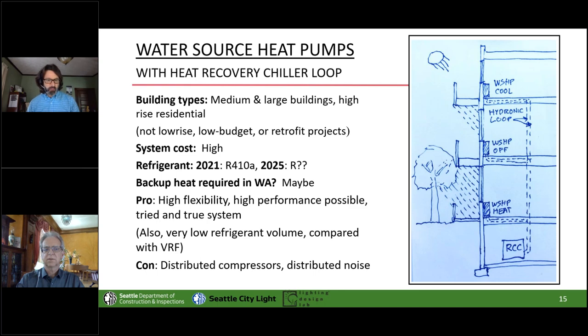Great. Now we're getting to the point where we've got these heat pump chillers, and we can do that heat pump chiller sitting down in the garage. Wonderful, because you've got all that ground going on, or up on the roof, and you can still do water source heat pumps. So when we get to that section where we say R410A, not long for this world, and we say, but what about VRF? It's not possible. That's got some answers of its own for VRF, but here's a viable alternative that's not radically more expensive, has the same flexibility, and still has that energy benefit of sharing heat around the building.